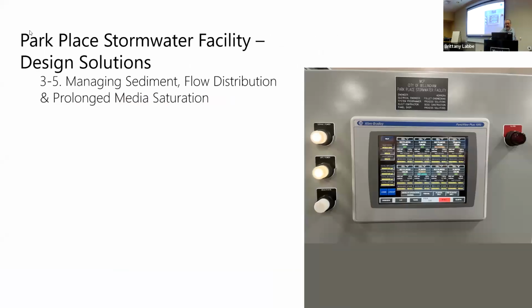So there's a whole bunch of really, really fun things that you can do when you have a brain at your stormwater facility. Really, it was the use of that PLC that solved the management of sediment, because we programmed it to drive the cells into ponding. As the flow comes up, it's programmed to send 100% of the flow to a cell, right to ponding, pushing water over the entire surface area of the facility and maxing out its capacity before we turn on the next cell as the storm comes. And so that allowed us to solve our flow distribution issue, because it's not a problem anymore. We're going to just drive that cell into ponding, and with cells and basins this big, we can do that. So our facility is going to be in ponding more often than a typical facility, engage more media, spread that sediment out, engage more mulch. And then we can also turn them off and address this prolonged media saturation question.